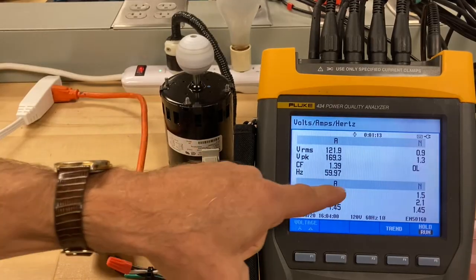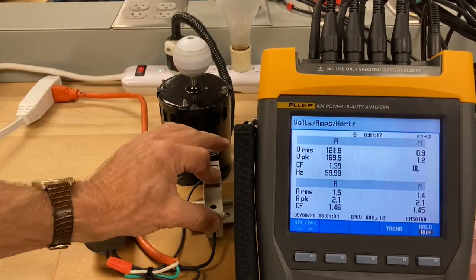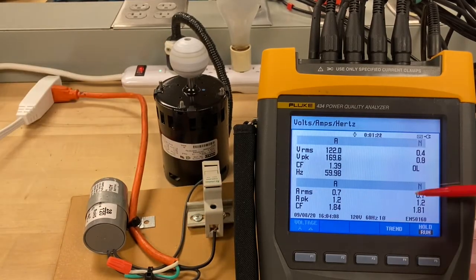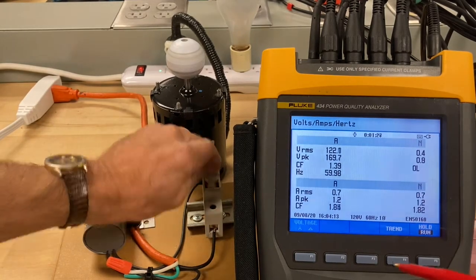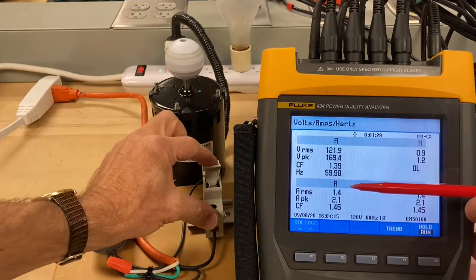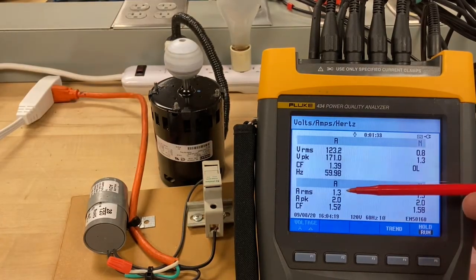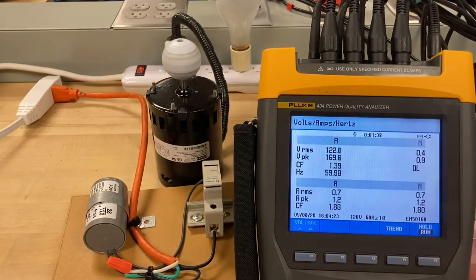Turn the motor on, there's 1.4. But if I add the capacitor, I have them both on, and it went down to 0.7 amps. Just the motor, 1.4. Just the capacitor, 1.3. Put them both on, I got 0.7.